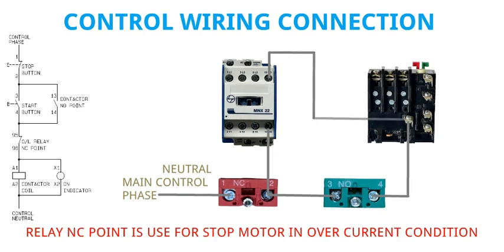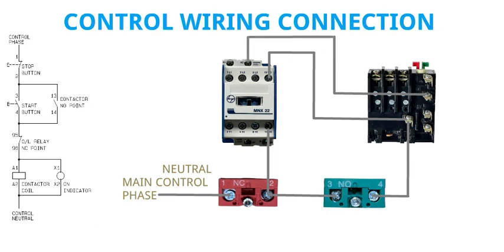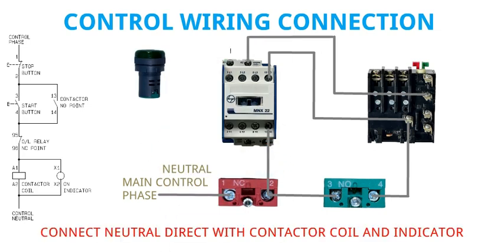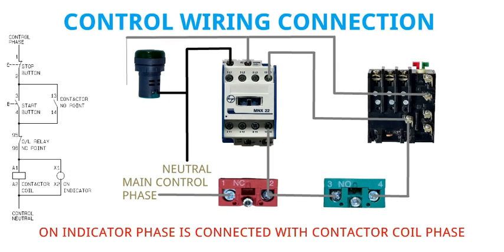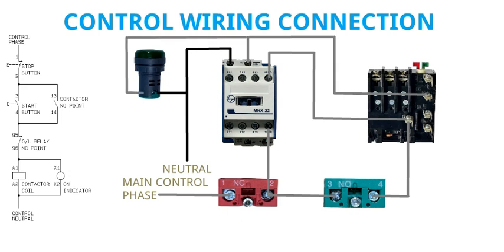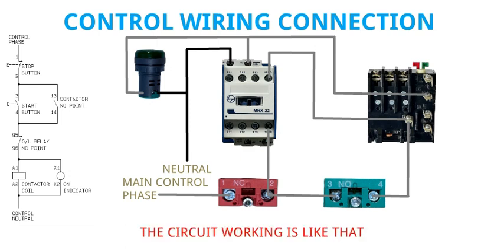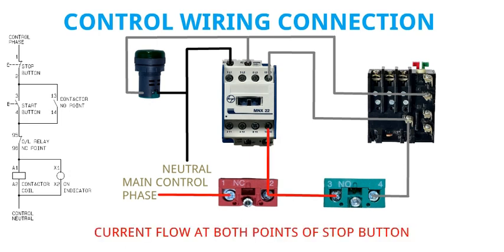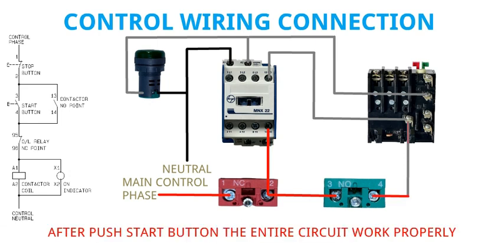The contactor NO point is used for holding purpose. The relay NC point is used to stop the motor in an overcurrent condition. Connect the neutral directly with the contactor coil and indicator. The on-indicator phase is connected with the contactor coil phase. The wiring circuit is now complete. The circuit works as follows: when we switch on the control supply, current flows at both points of the stop button. After pressing the start button, the entire circuit works properly.